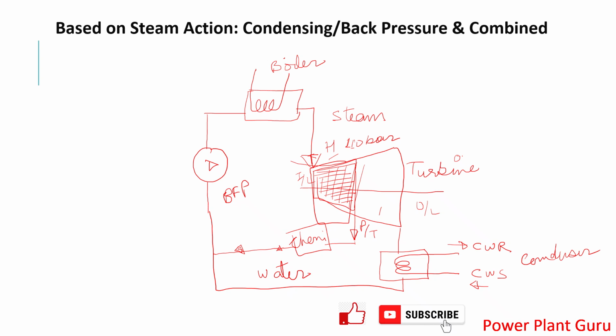So this is what a back pressure turbine is. But now many a time it happens that in a process plant you don't have exactly this kind of setup where you need only process. Sometimes your process is down. Let's say your process is down, you don't need that steam as of now. Then what will you do? You cannot stop this turbine, right? Because you need that power again for many other purposes. Maybe some essential power load is there, and you cannot stop and start the turbine frequently.